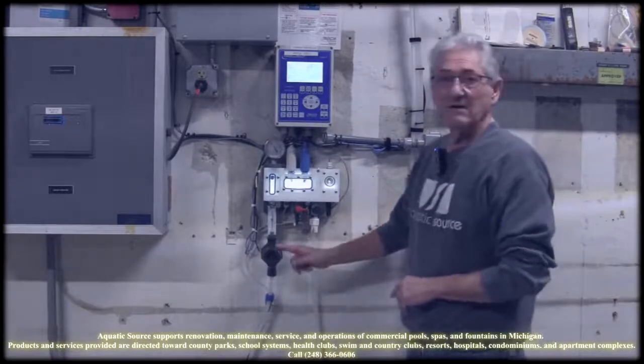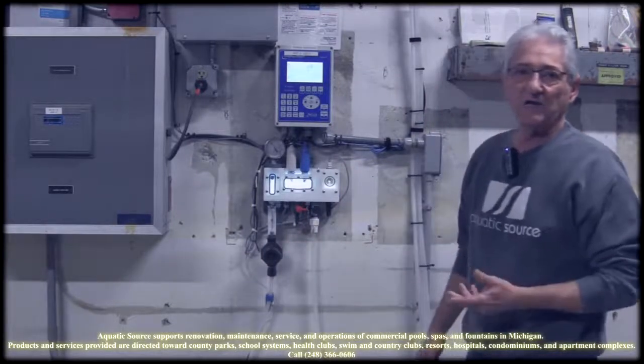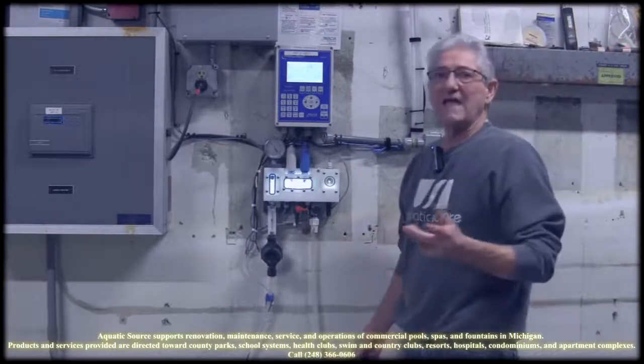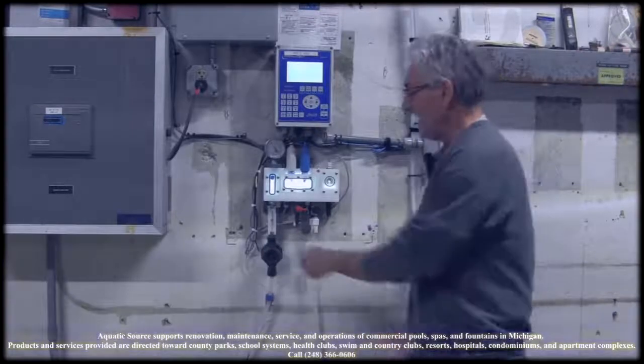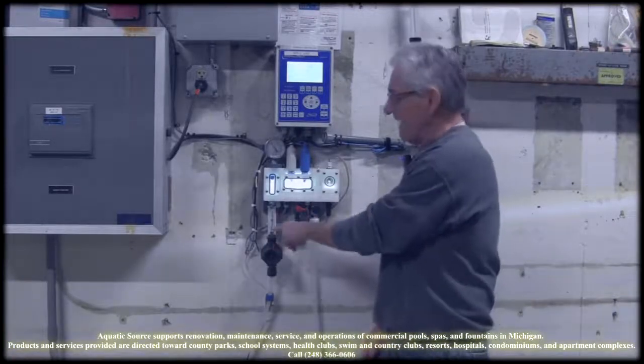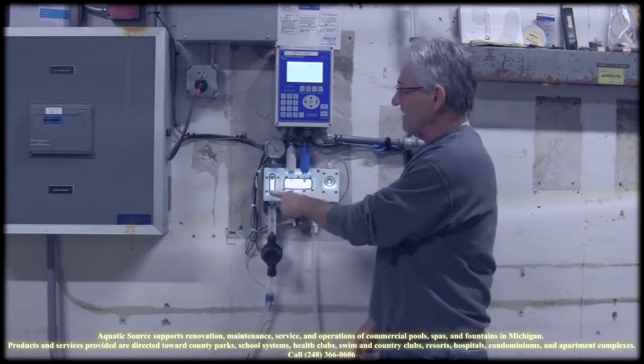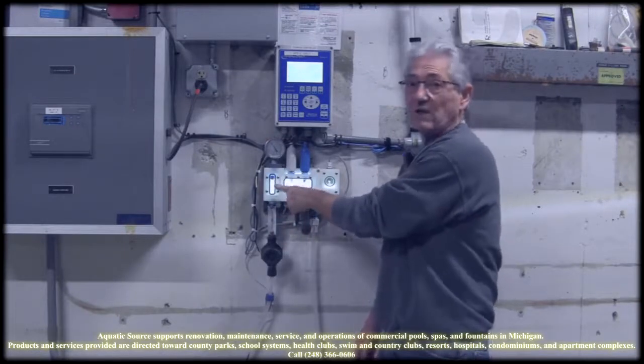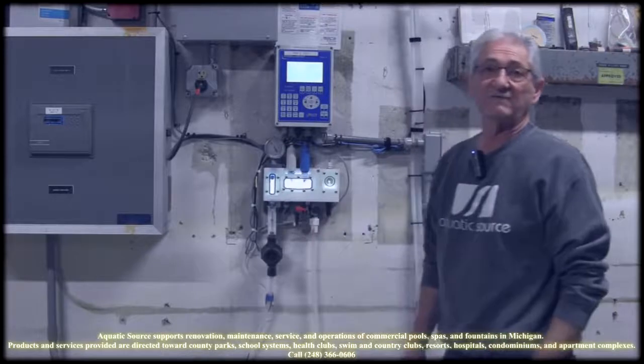We also have the Y strainer that periodically you're going to have to check because anything that gets through your filter system is going to stop this, drop the flow, and when it drops this lighted flow cell has the flow here that will actually turn this red telling you there's not enough flow.